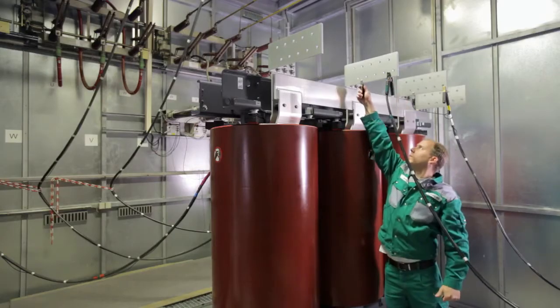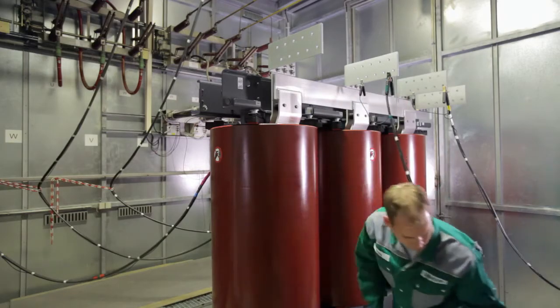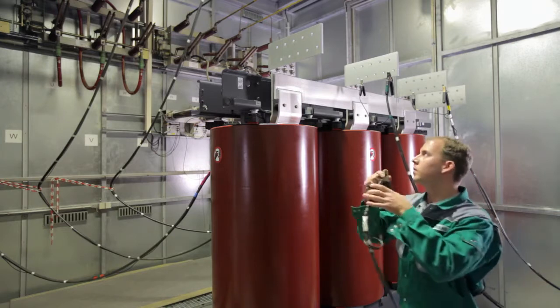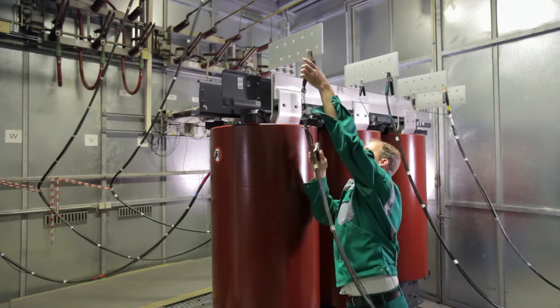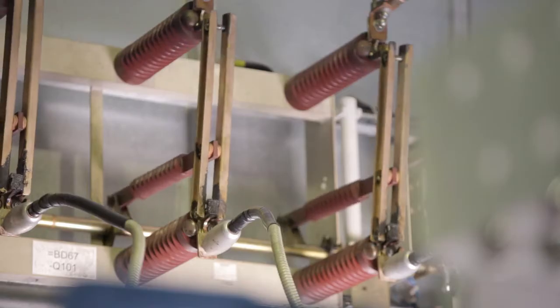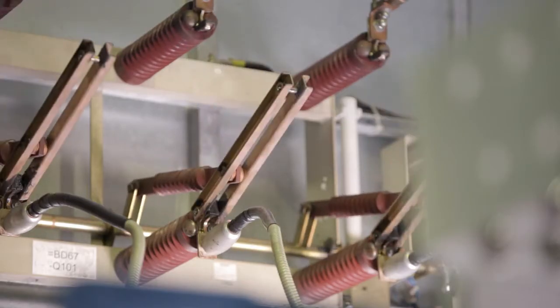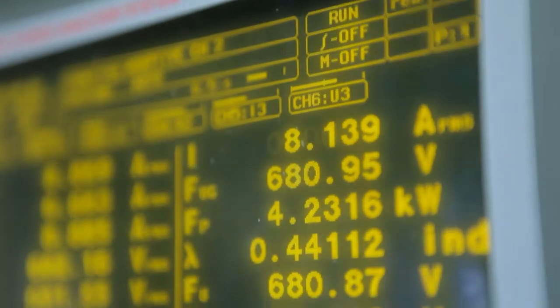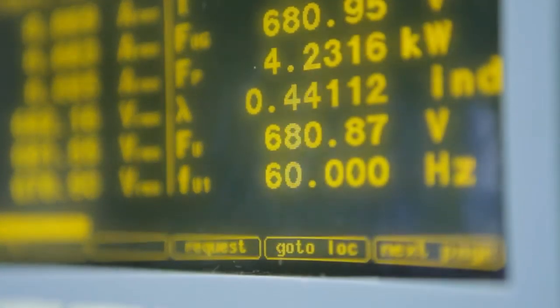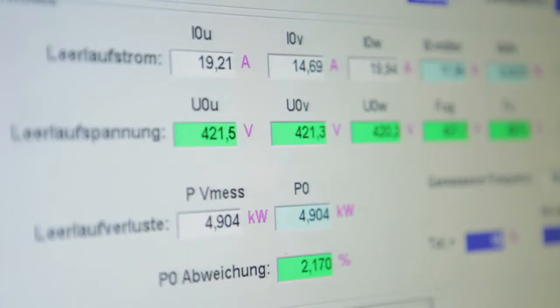We conduct nearly all type testing in our very own test bay, whether for lightning impulse tests or measuring noise and heating levels. Every single transformer is tested with up to twice the rated voltage to verify it is free from partial discharges. And just about every time, all readings show the green light.